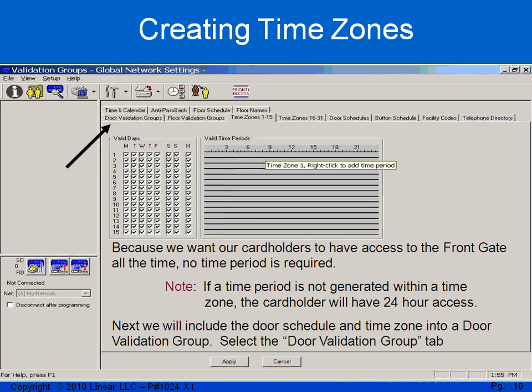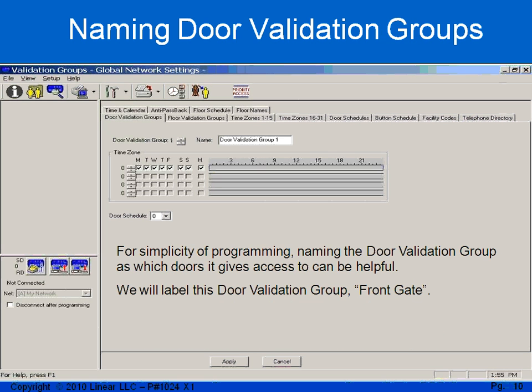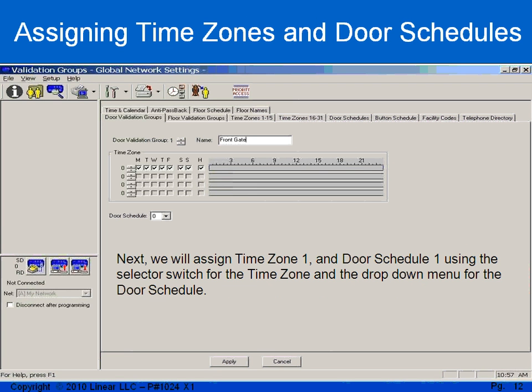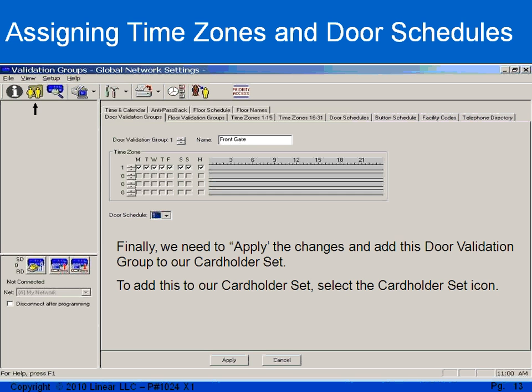Next, I need to take my time zone and my door schedule and roll it into a validation group. I like to name the validation groups as to what door I'm actually getting access to — it will make it simpler when I'm assigning these to cardholder sets. I'm going to call this validation group front gate. I need to roll in the time zone and the door schedule to that validation group, so I'll select time zone 1 and door schedule 1.